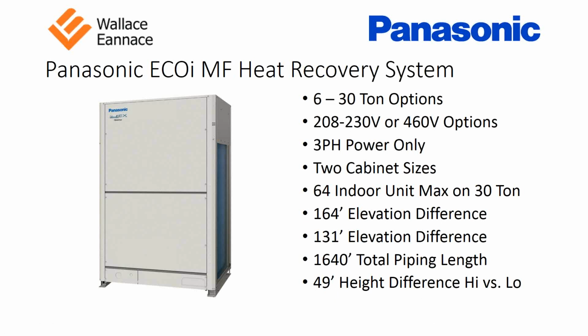Okay, this is our Panasonic ECOi MF heat recovery system. We offer this system in 6 to 30 ton options. It's 208, 230 volt, or 460 volt, and it's 3-phase power only. A heat recovery system is different than a heat pump system. Heat recovery systems allow you to simultaneously heat and cool spaces at the same time. So we have indoor units that are going to be connected to this condensing unit. Some of our indoor units with a heat recovery system can be in heating mode, and other indoor units connected to the system could be in cooling mode.